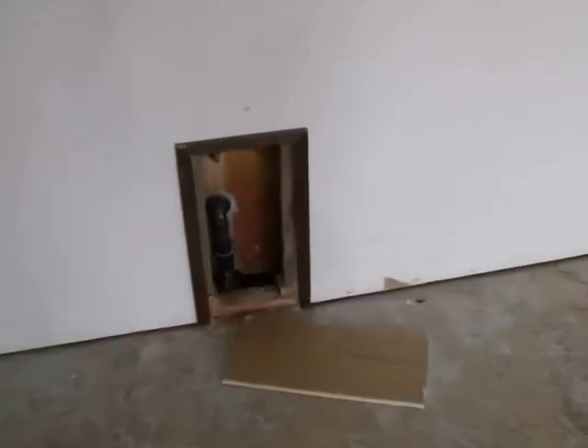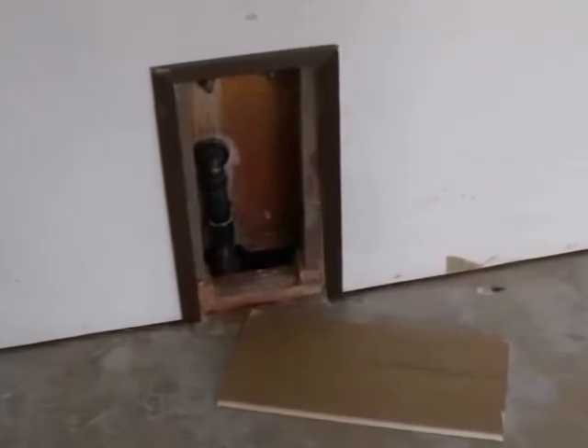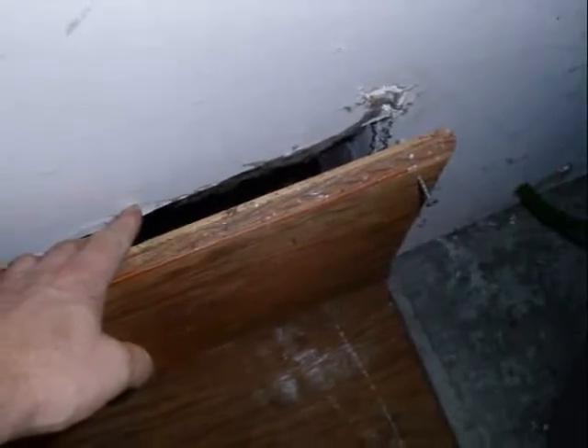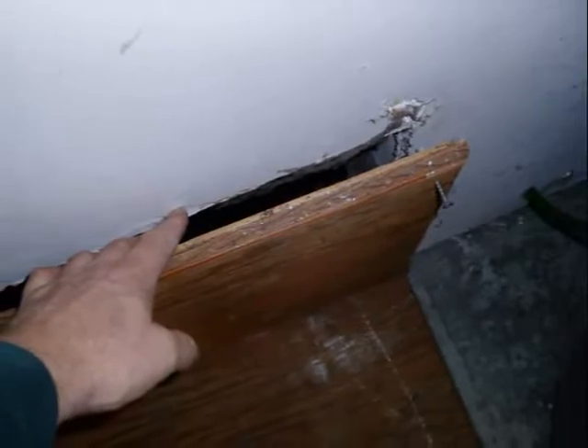Openings and damage, breaches in the fire resistance are common at not only ceilings but at walls as well. Sometimes the crawlspace hatch that leads down into the substructure of the home is in the garage, and the hatch cover is made of a combustible material.